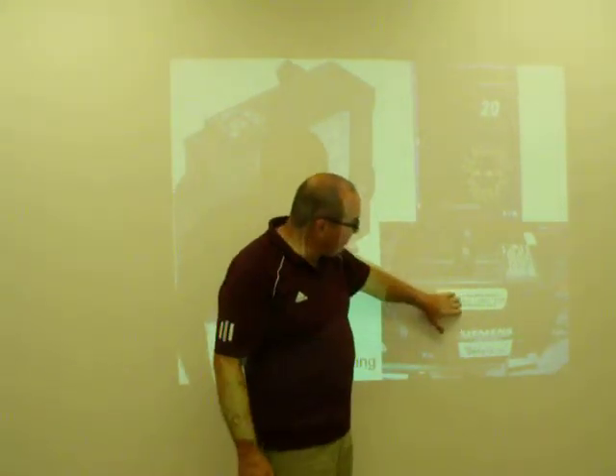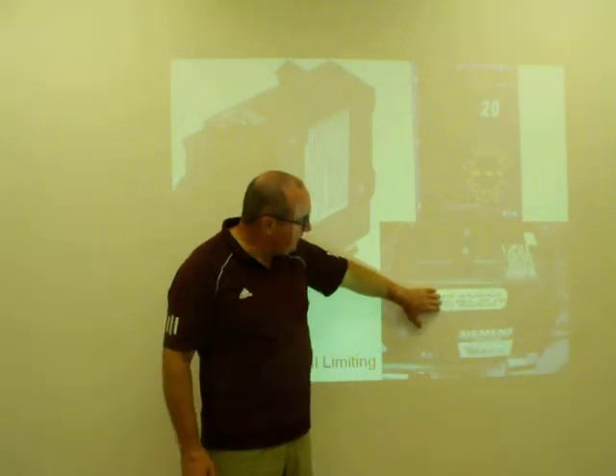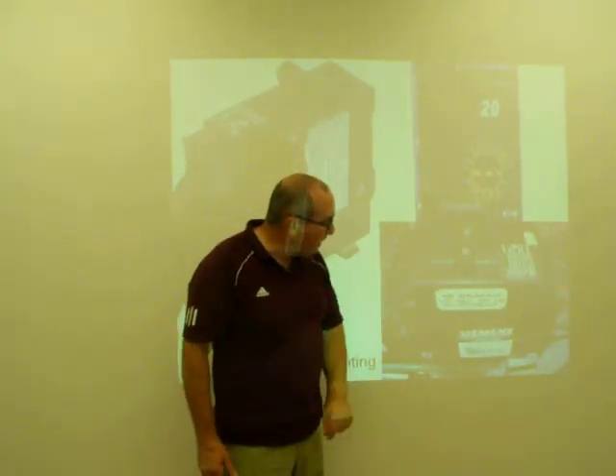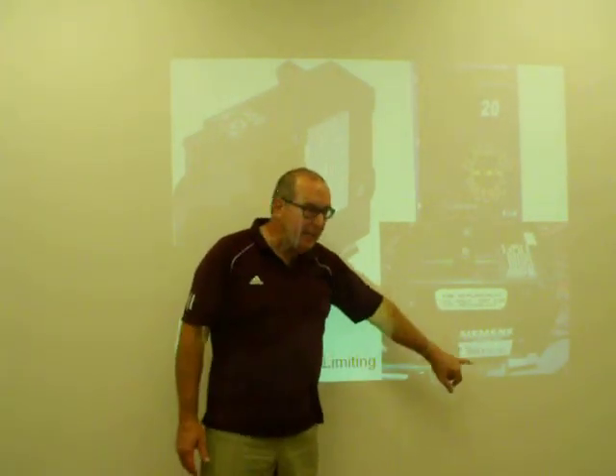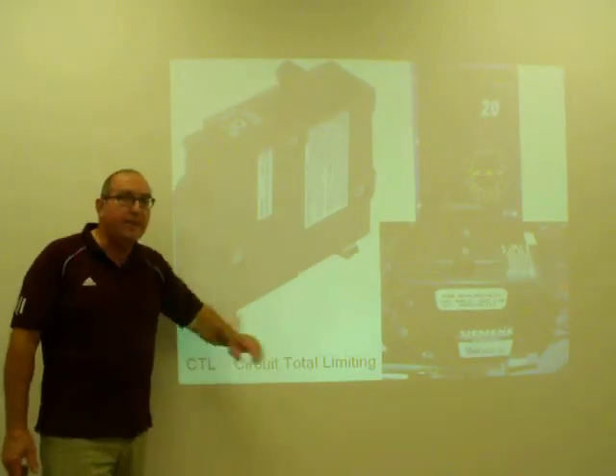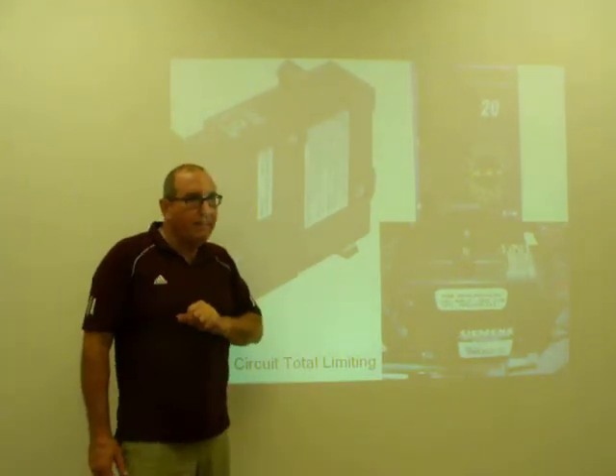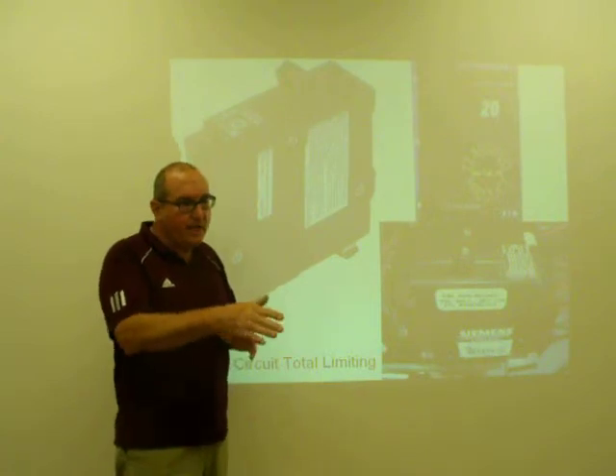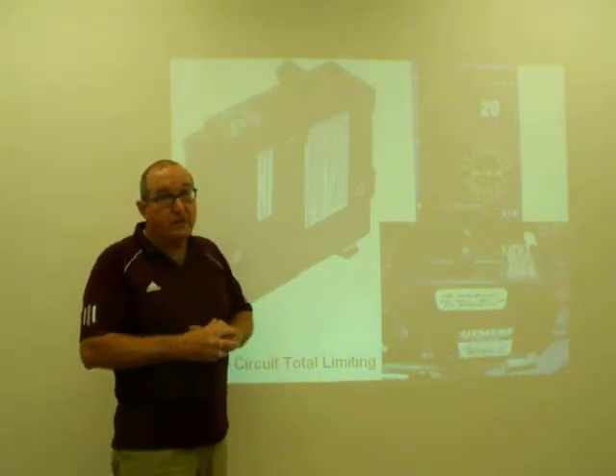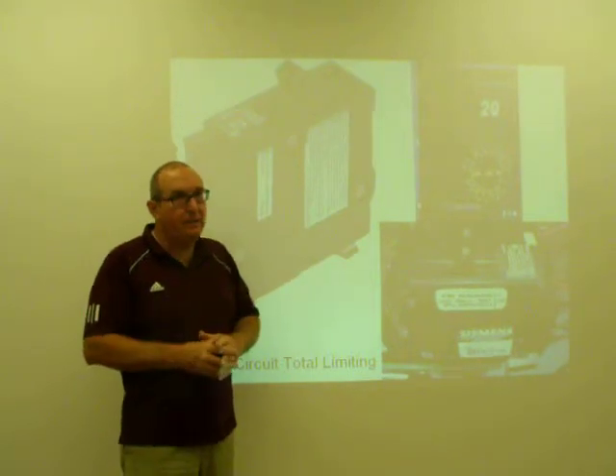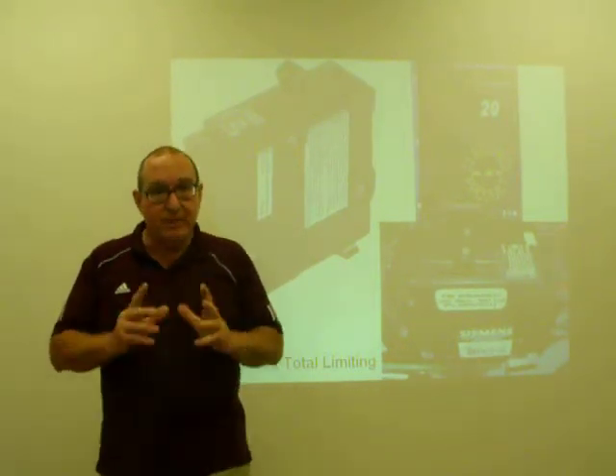And you'll also see labels like this on the side of the breaker that will say for replacement use only, not for CTL assembly. CTL is circuit total limiting. That means that you have a panel that has those types of limitations physically installed that are designed to prevent you from exceeding the total number of circuits that panel is listed for.